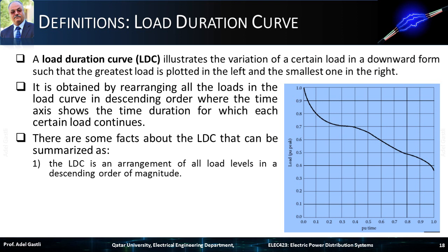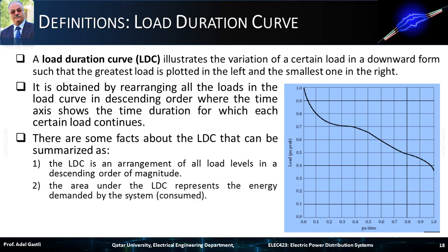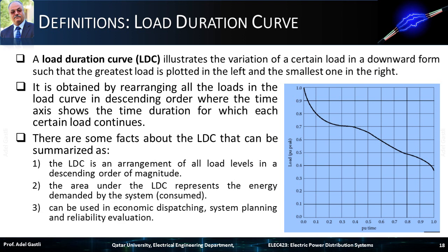There are some facts about the load duration curve: 1. It is an arrangement of all load levels in descending order of magnitude. 2. The area under the load duration curve represents the energy demanded or consumed by the system. 3. It can be used in economic dispatching, system planning, and reliability evaluation. 4. It is more convenient to deal with than the load curve.